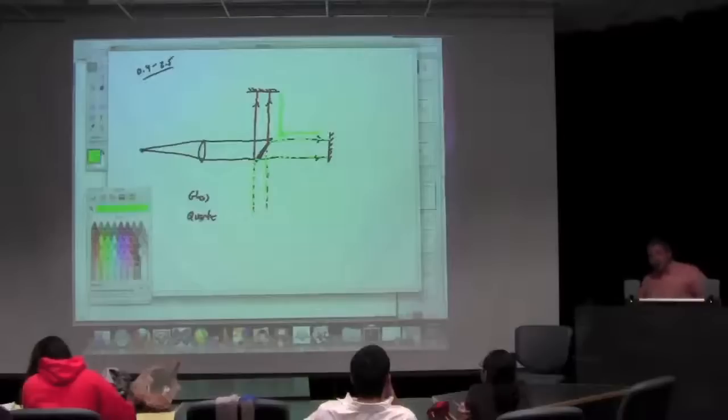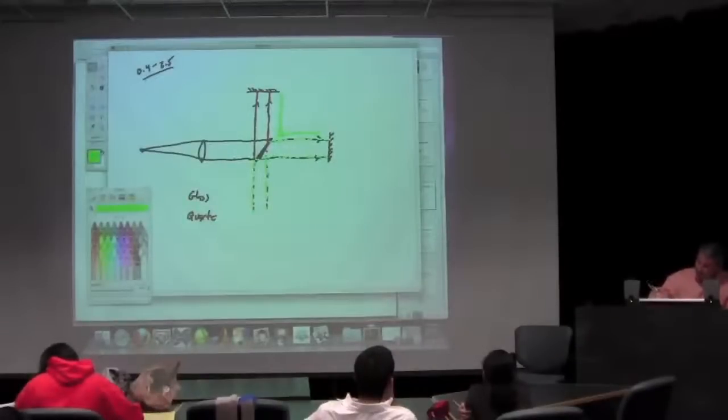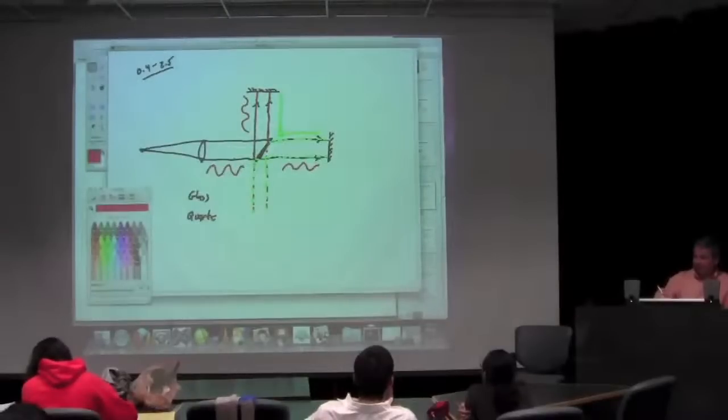So what we're doing here is a destructive and constructive interference sort of thing with the light. If I represent a single wavelength, so let's say we're using red, if I have a red wave coming in, that red wave is going to pass through, and it's going to get put up this way also. Depending on where I place these mirrors, if I place them exactly the same distance away from that beam splitter, I'll get perfect reflections of the waves, and they'll recombine perfectly at this point.